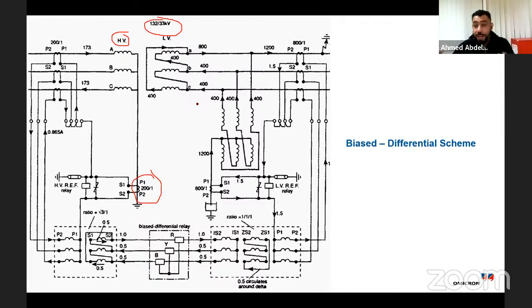To compare between two values, I should have a reference. I can't compare 1,000 with 1 million, because I don't understand what I'm comparing against. If I say 1,000 relative to 1 million, it's a great difference. But if I say 1,000 compared to 1, then 1,000 is a great value, and 1 million is also a great value. So I should have a reference. The reference in the electrical system or in the transformer you should define before the numerical relays, in a static relay, which we can call the high impedance relay. This is a high impedance differential protection. We are doing every mathematical calculation outside the relay, and finally we are giving the relay current which is ready for comparison.